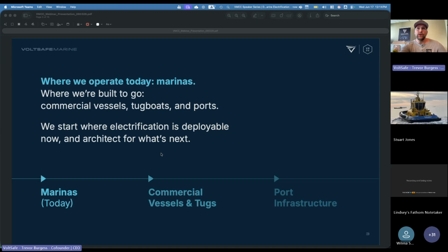Our technology in the past, we had been developing it, and right now we are just finishing safety certification, and starting to fulfill many of the earlier pilots we did last year to get feedback from marina operators and stakeholders to deliver a platform that is plug and play hardware pedestal that is much safer, much simpler to operate, has a beautiful user interface that easily twists and disconnects, and always is safe, along with some real key code changes happening in Canada on the CEC side, the Canadian Electric Code, and in the US even more so, the National Electric Code, around leakage and ground fault protective equipment, typically mandated in the form of the breakers within each pedestal for each slip.